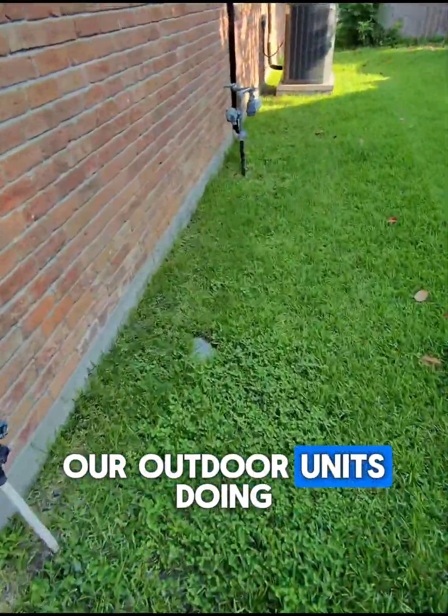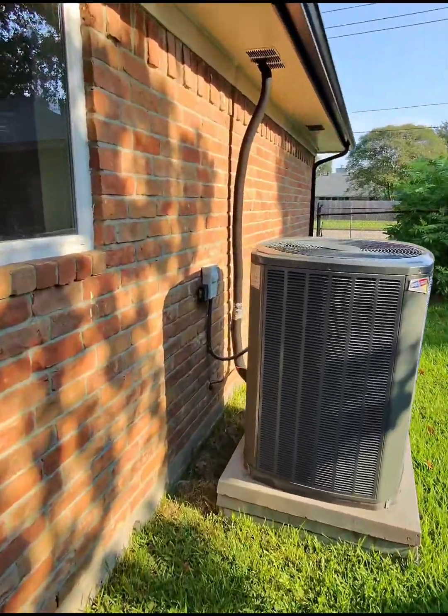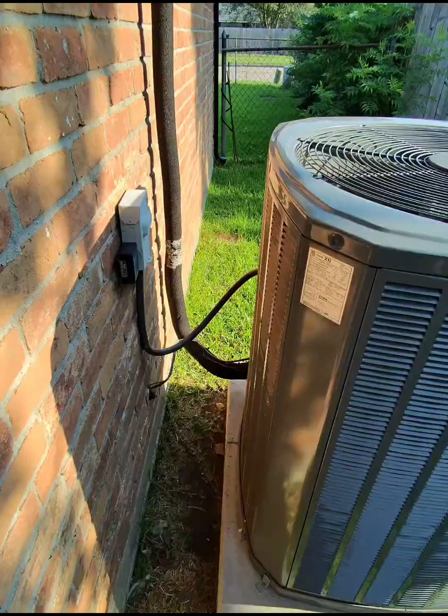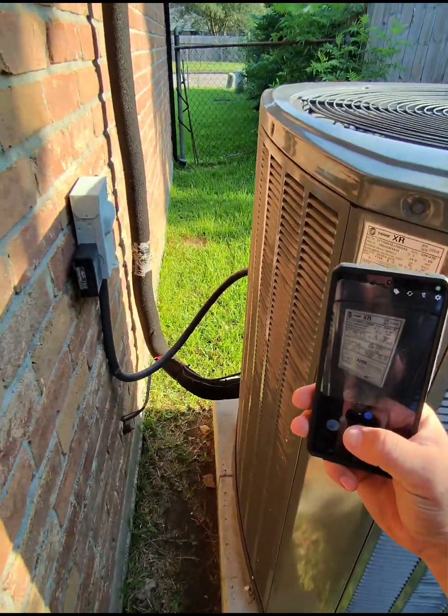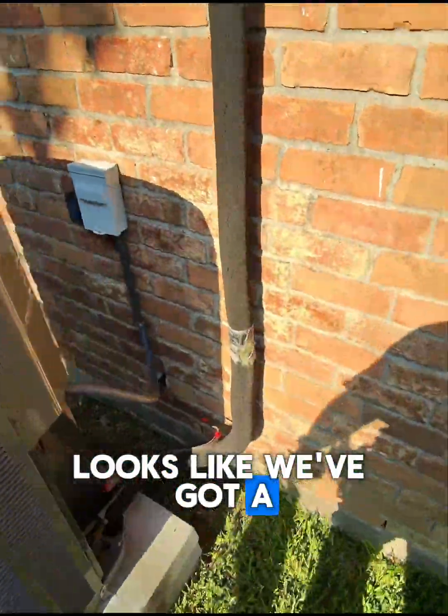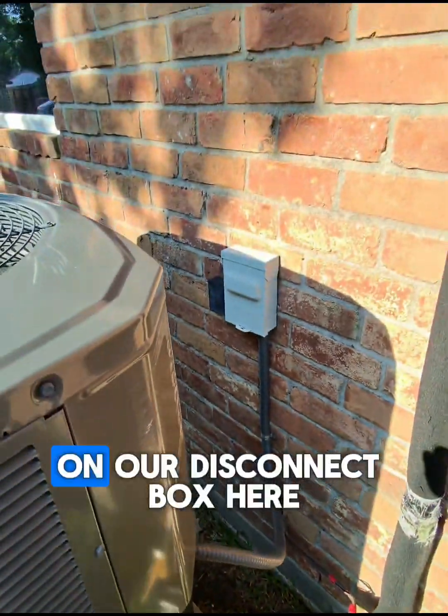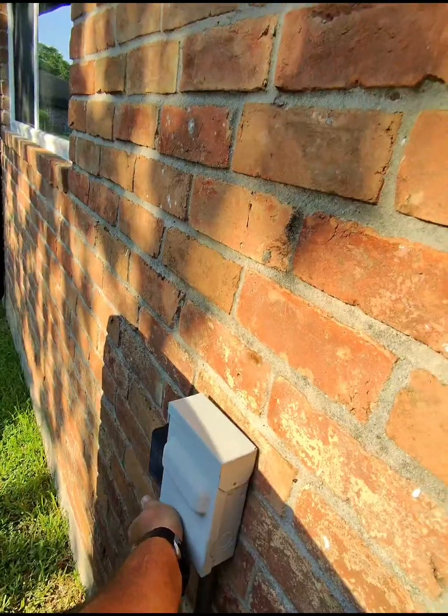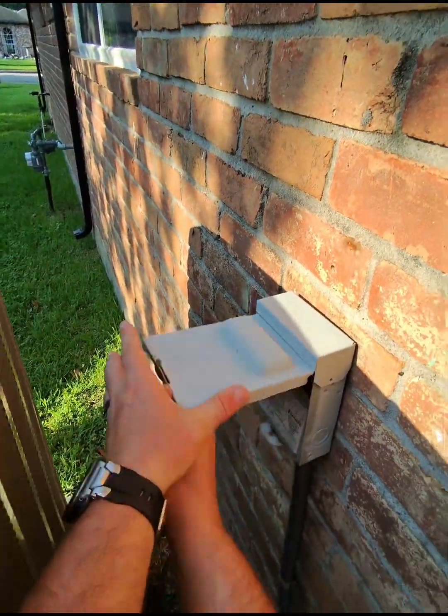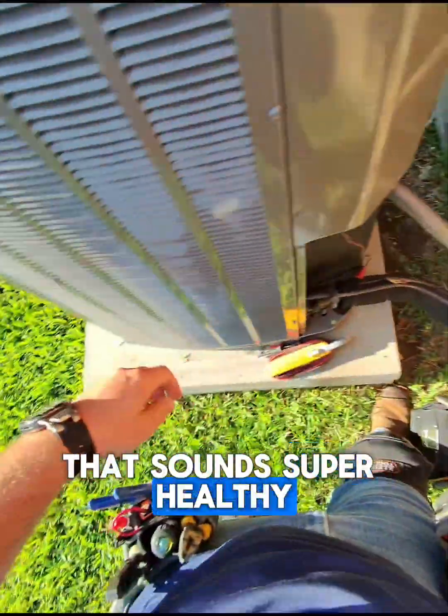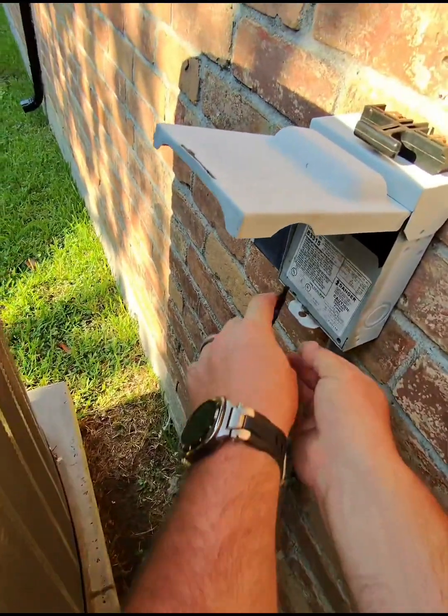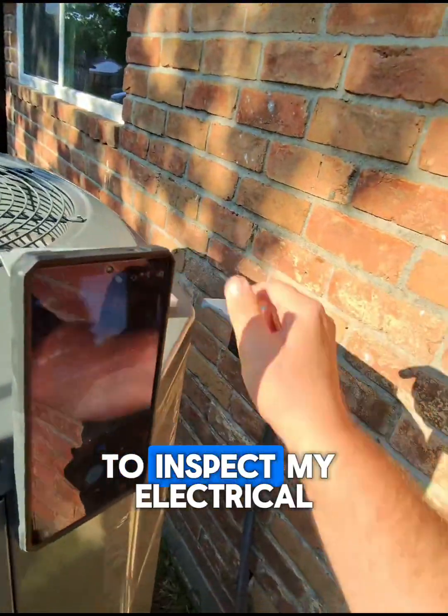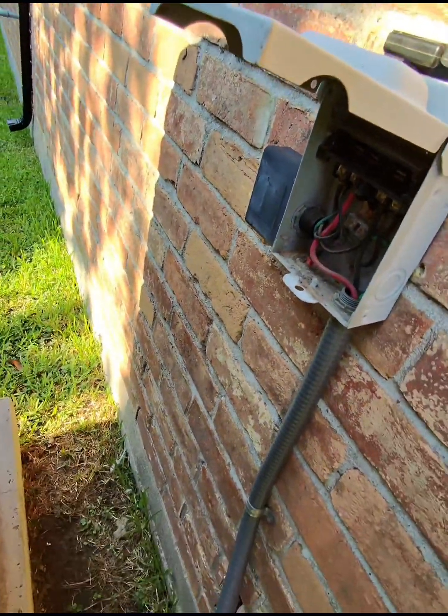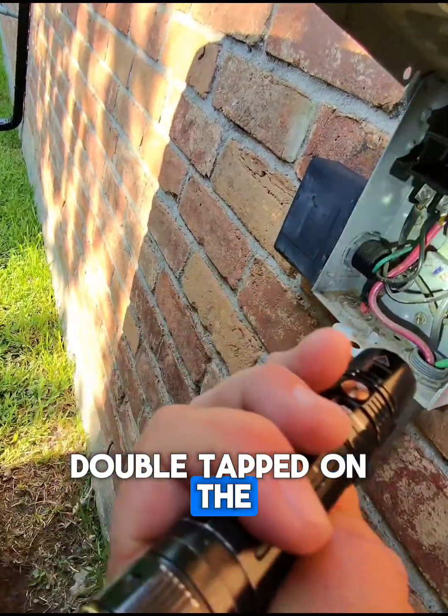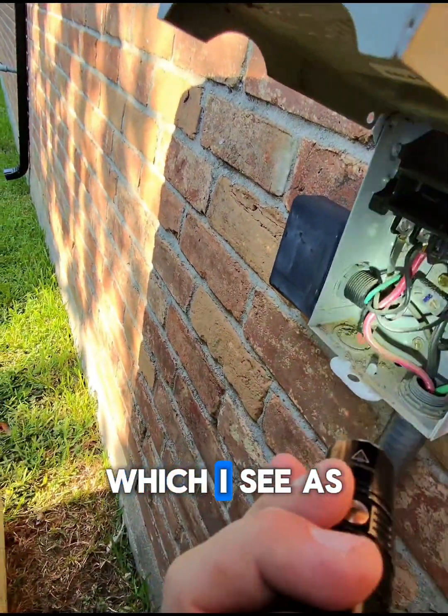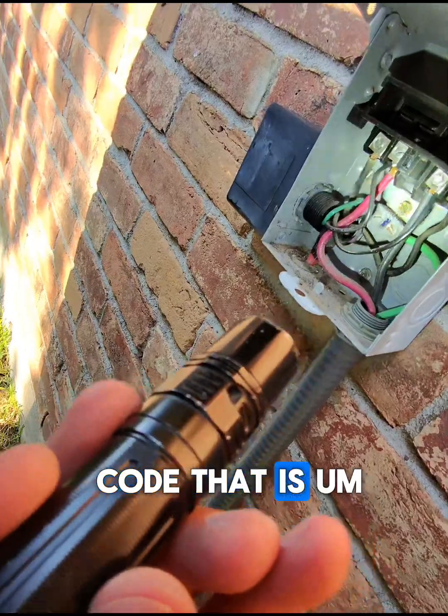Alright, let's see how our outdoor unit's doing. '18 model. Record our model serial number. 4 tons. Looks like we've got a surge protector on our disconnect box here. That sounds super healthy. I have to inspect my electrical connections here. So they've got this surge protector double tapped on the load side of the disconnect, which I see as common practice, but from what I understand with the National Electric Code, that is not very kosher.